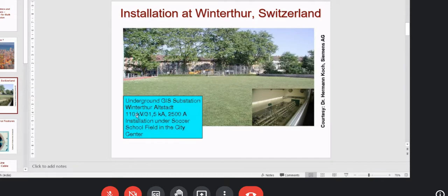It's 110 kV with a current rating of 2.5 kiloampere. So 110 kV into 2.5 kiloampere, you can calculate the megawatt. You can clearly see 25 into 1.1 is 27.5, so it is 275 megawatt capacity. And this is an old city. This is not a modern city. So the power requirement is 275 megawatt.